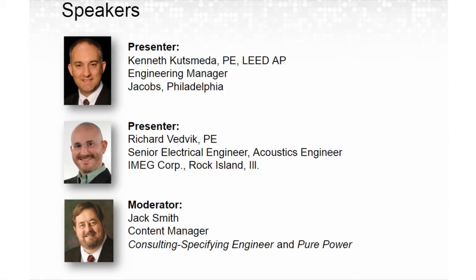When we look at core losses, which are essentially load independent, that's more of how the unit is constructed. And from what I can tell, looking at the ways transformers are constructed, I think the increase in cost that we see to increase energy efficiency, and certainly the 2016 Department of Energy increases did increase overall transformer cost, is evidence that as we increase efficiency, we do increase robustness and therefore reliability.